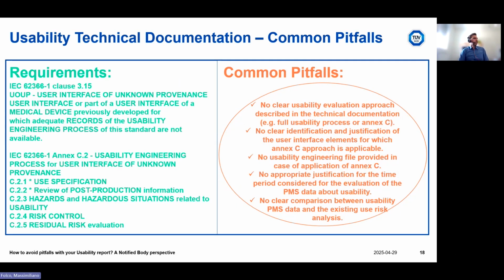Let's move to the concept of UOUP, user interface of unknown provenance, that is defined in clause 3.15 of the standard as follows: user interface or part of a user interface of a medical device previously developed, for which adequate records of the usability engineering process of this standard are not available. So this is a user interface or a part of a user interface which has been developed before the entry into force of the 62366-1 2015 standard, so for which no appropriate records of the usability engineering process are available. The standard gives an alternative approach to the manufacturer for giving evidence of compliance of that device to the usability evaluation process.